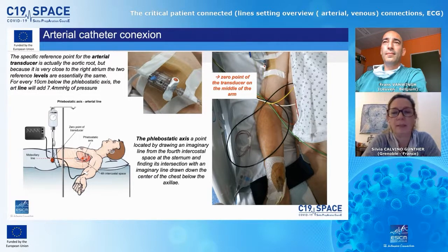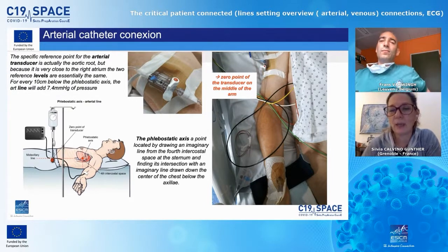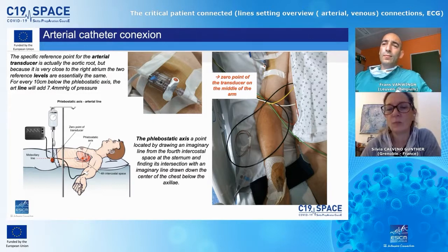In our unit, to avoid this complex situation, we put our 0 point of the transducer on the arm when the patient doesn't move, and so it will always remain at the level of the aortic root or the phlebostatic axis. The problem is when the patient starts to move, especially the arms. When the patient doesn't move, if the bed moves or if we have to sit the patient up a little bit more, it will always remain in the same place.